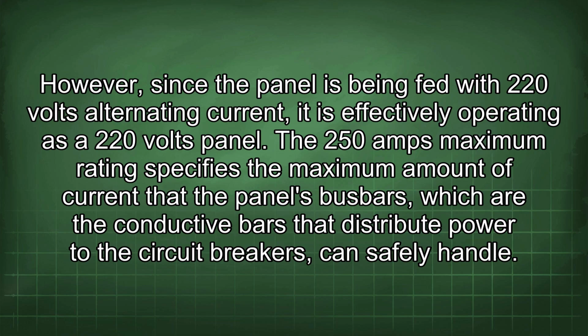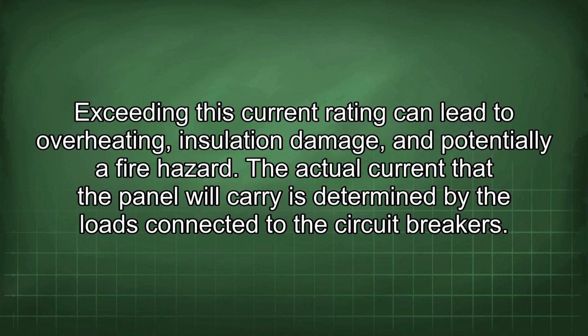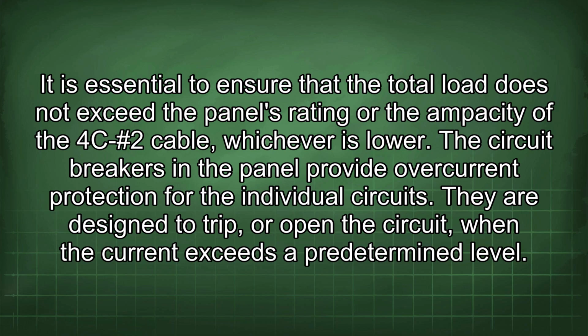The 250 amps maximum rating specifies the maximum amount of current that the panel's busbars, which are the conductive bars that distribute power to the circuit breakers, can safely handle. Exceeding this current rating can lead to overheating, insulation damage, and potentially a fire hazard. The actual current that the panel will carry is determined by the loads connected to the circuit breakers. It is essential to ensure that the total load does not exceed the panel's rating or the ampacity of the 4C-#2 cable, whichever is lower. The circuit breakers in the panel provide overcurrent protection for the individual circuits. They are designed to trip or open the circuit when the current exceeds a predetermined level.